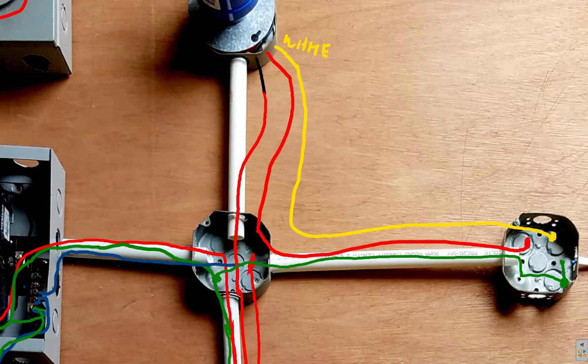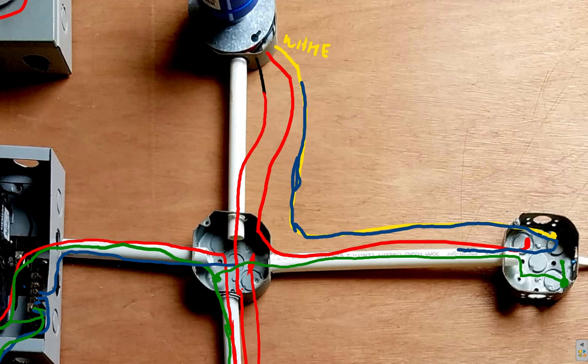Now this white neutral, I'm going to draw the neutral wire blue. Let me just draw this blue. Remember, the color is yellow, but I'm assuming it's white. So this neutral, you must have a wire from it running back to the main neutral. You could have another wire joined somewhere here or here, wherever it is, and tie it with this neutral. Remember, this neutral is already coming from the circuit breaker on one circuit, so it's one line, and then you branch it to whichever neutral you need.